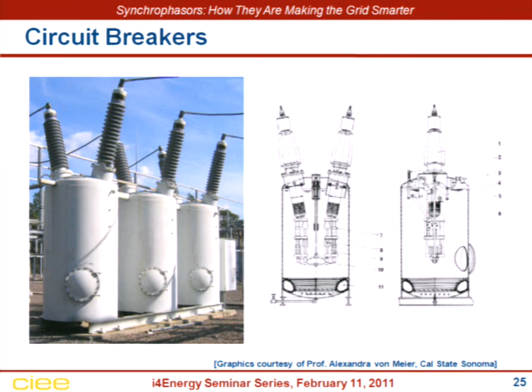The full load current goes through this thing, and these switches inside basically open up. They get signals from the relays. Relays used to be electromechanical devices, basically fancy solenoids - a current transformer would take a small percentage of the load current and put it through the relay. Normally the relay would just sit there saying nothing's going wrong, but as the current got to elevated levels, the solenoid disc would start to move, and eventually short some contacts, sending a signal to the breaker to open. This is not unlike a starter relay on a Ford car, for example.